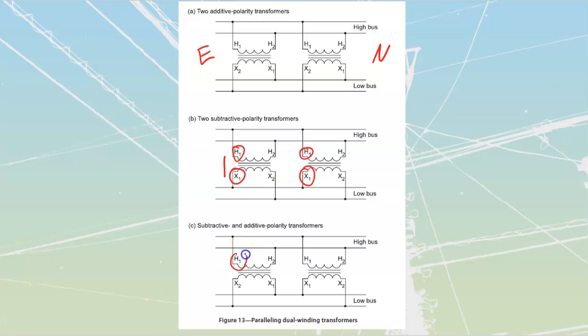Alternatively, if we already have an additive on here, we can parallel on a subtractive. All we have to do is watch our transformer polarity. If I've got the H1 connected to this line, H1 connected to this line, I'm just going to play matchy-matchy - that's all we're doing, it's like kindergarten games. Does this line have the X1 connected to it? Perfect, connect your X1 to it, and you cannot go wrong.